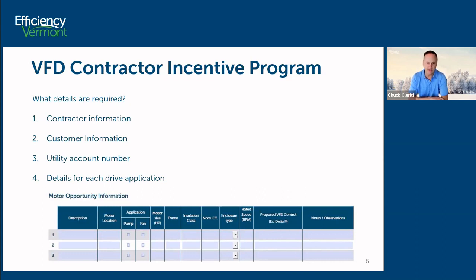And then some motor tag information: frame size, and insulation class is really important. You don't want to put VFDs on motors that don't have the proper insulation class. They need to be inverter duty rated. And this is just a way for us to verify that, yes, the motors are inverter duty rated. If not, it's not the end of the story. We could entertain a motor upgrade or a smart pump that has an integrated IE5 motor and VFD along with it. Then the nominal efficiency on the motor tag, the enclosure type, the RPM.